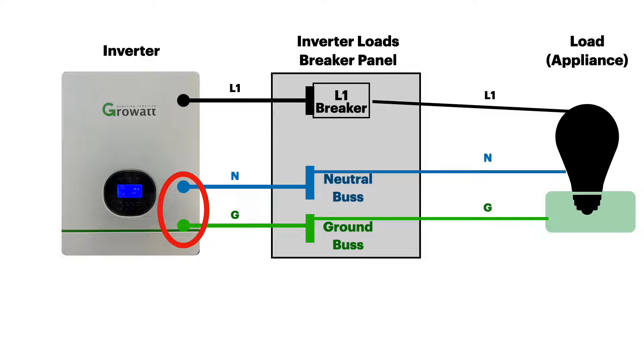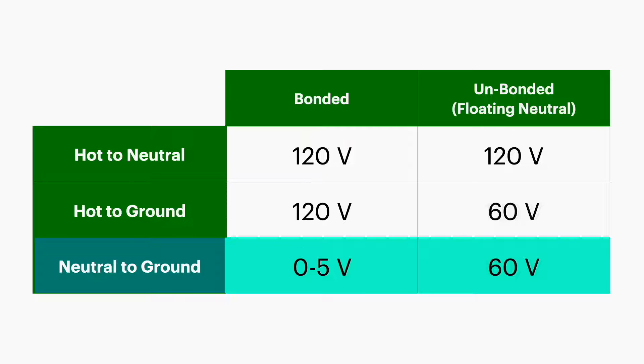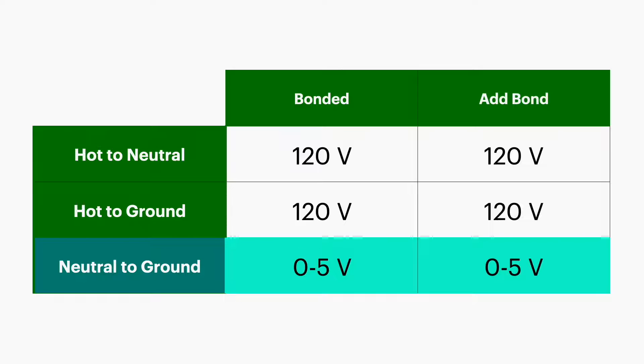All we need to do is put a neutral-ground bond either in the inverter or in the breaker panel, and then all of our voltages will read the way they should. This applies to a lot of inverters, especially all-in-one inverters and larger standalone units — things like Sol-Ark, Growatt, EG4s, MPP Solar, and so forth.